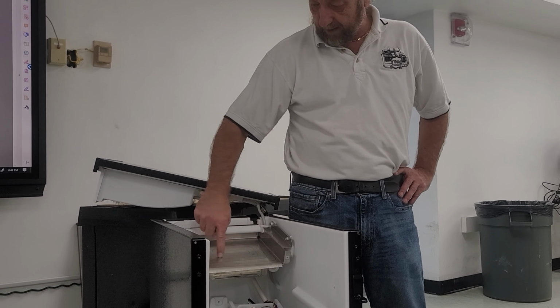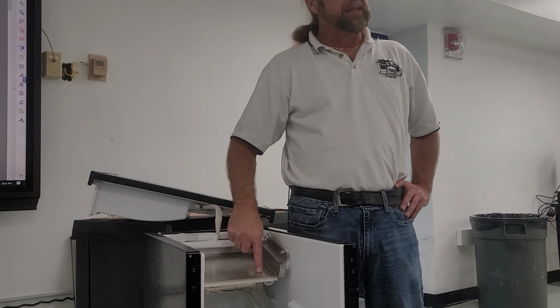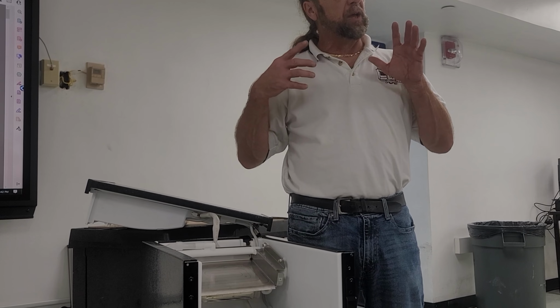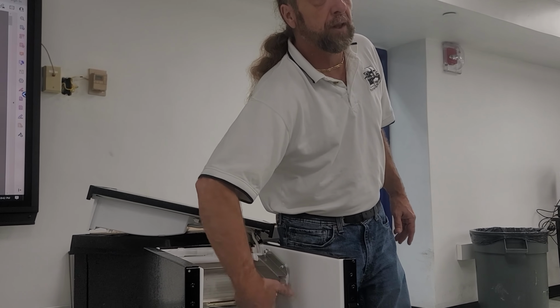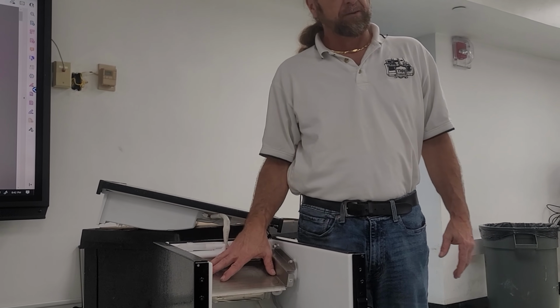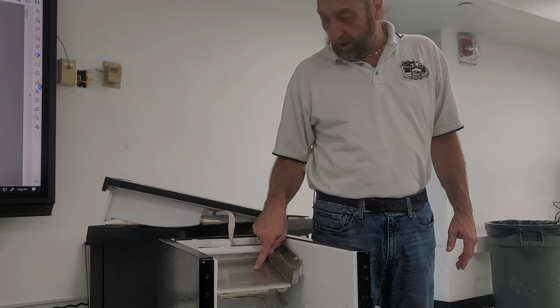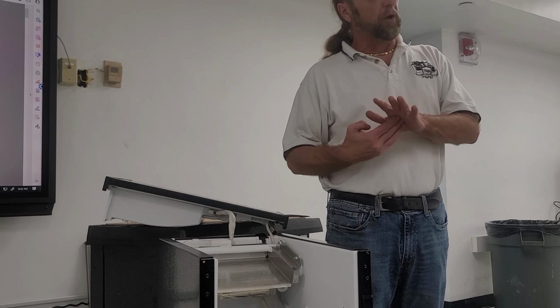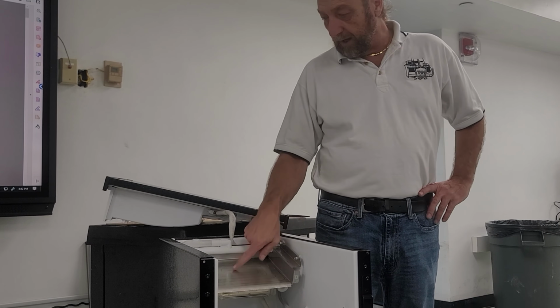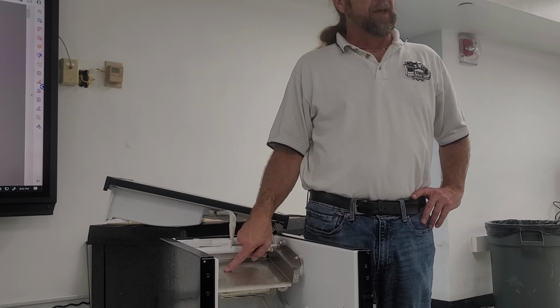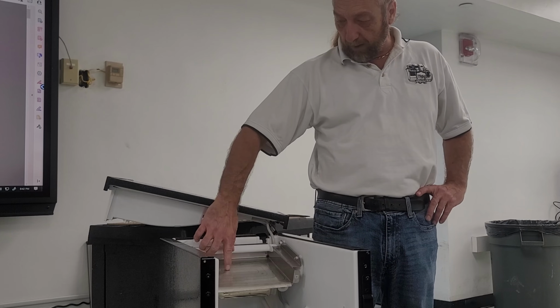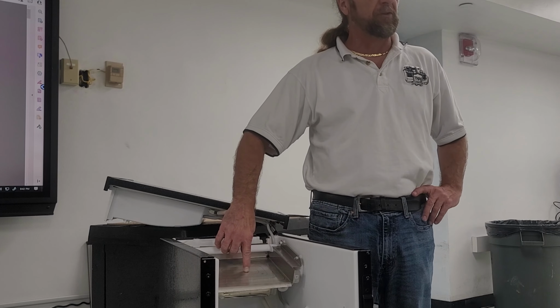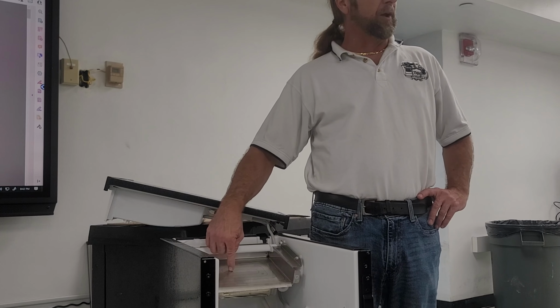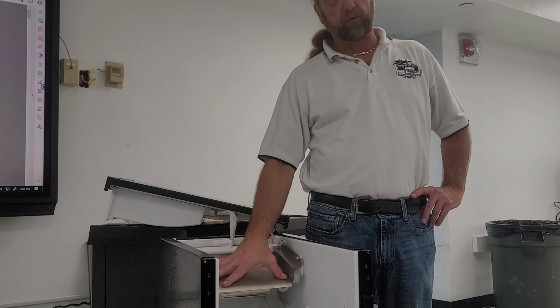These lines here is because they sort of weld the refrigerant lines that are underneath here to this plate. So those lines are actually where it is welded to the plate. But it's almost like it rusts. And over a period of time, I've seen right here on these two end points, I've seen it rust and freon leak out. And we have to replace the evaporator.